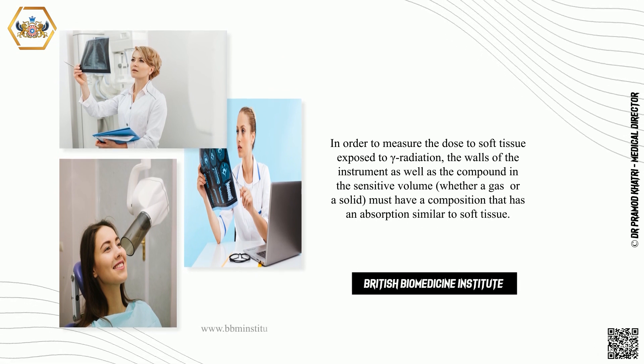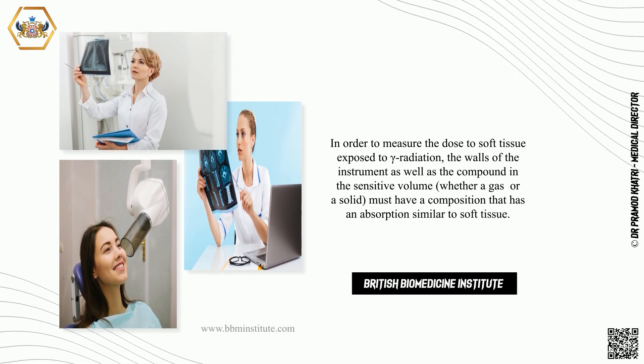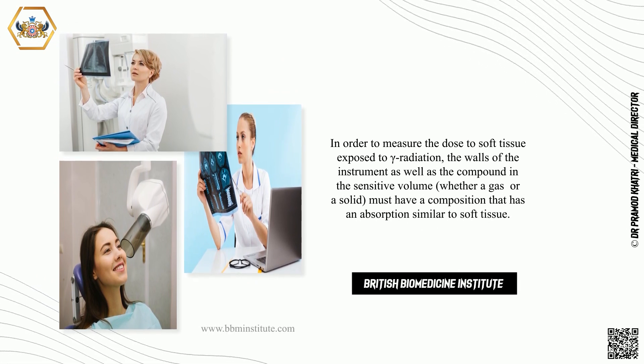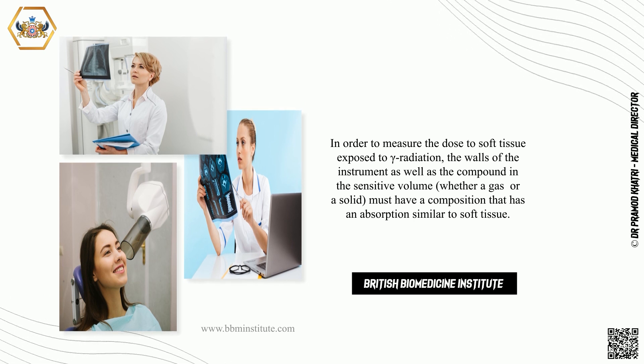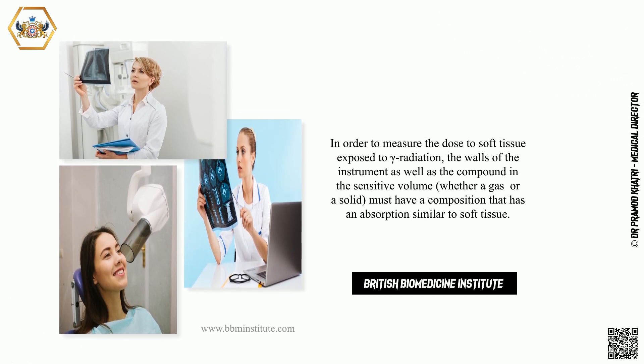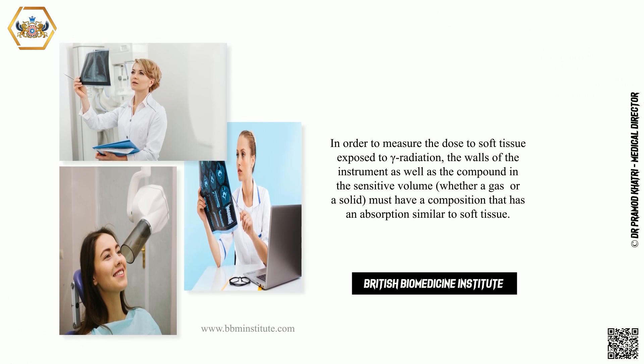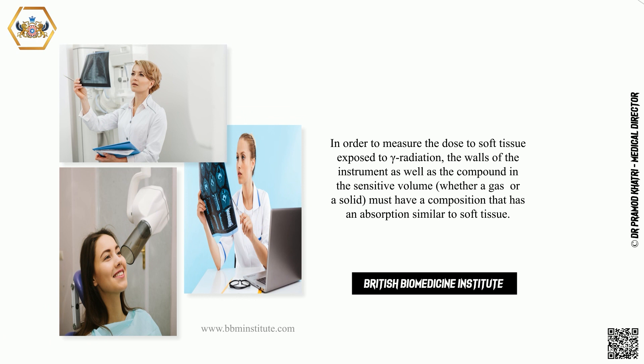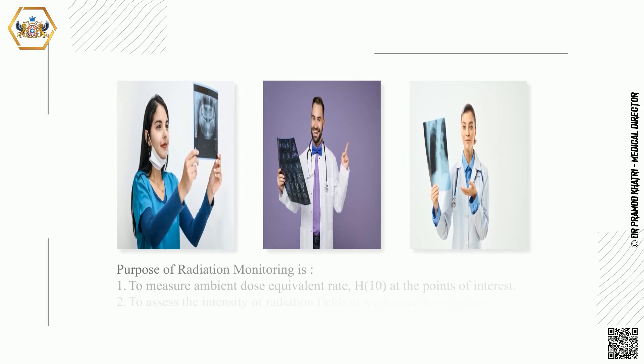In order to measure the dose to soft tissue exposed to gamma radiation, the walls of the instrument as well as the compound in the sensitive volume, whether a gas or a solid, must have a composition that has an absorption similar to soft tissue.